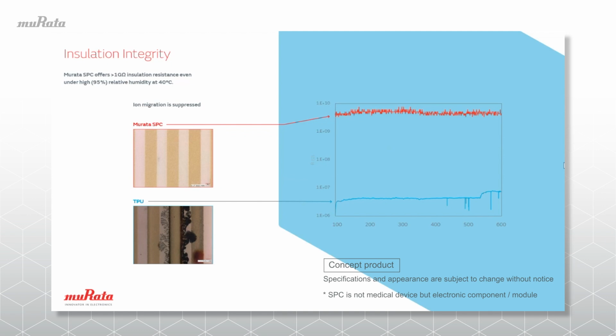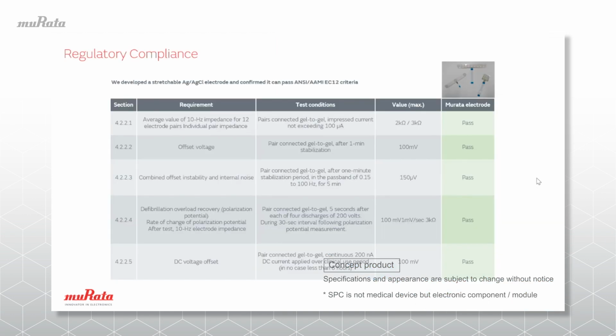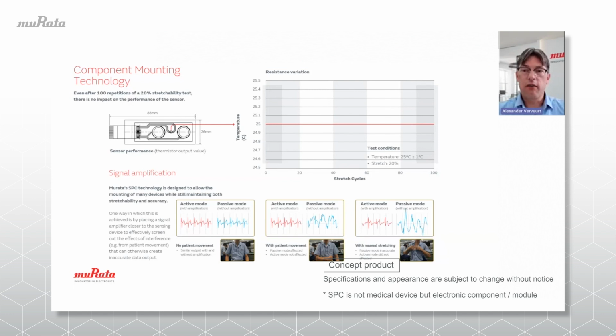Murata stretchable printed circuit has been designed to avoid ion migration as much as possible and ensure robust performance for long periods of time in high humidity and high temperature. The technology platform covers integrating various printed stretchable materials, and one of these is silver chloride for electrodes. Silver chloride is the standard material used for electrodes such as ECG, EEG, and EMG. And we have tested the electrodes according to the relevant regulatory standard, EC12, which is the main industry regulatory standard for disposable ECG electrodes. But it's also used for other bioimpedance patient monitoring devices. Our test results show that our stretchable printed circuit electrode technology meets the different performance and safety requirements within EC12.